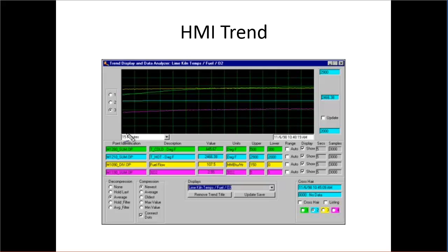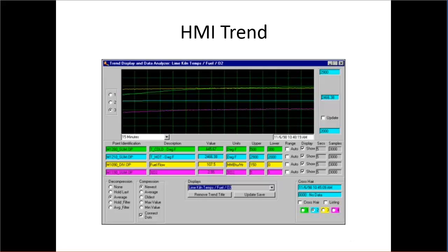Here's where the tags come in. You can see the different colors of the tags, and these are tags in the system. You can see right here that this is a temperature in degrees Fahrenheit — it's got the tag name, the descriptor, the current value, and the engineering units. This shows you what we talked about in the telemetry unit: the importance of the metadata that comes along with the tags, so that when you're looking at a display, you know what tag you're looking at, you get a description, you can see the value, and you get the engineering units.